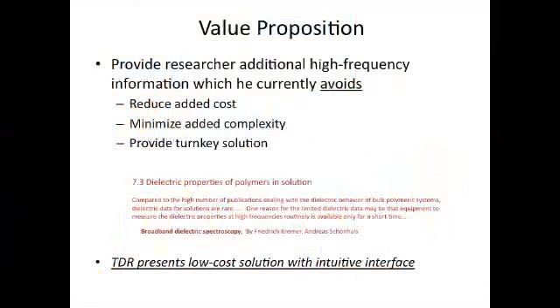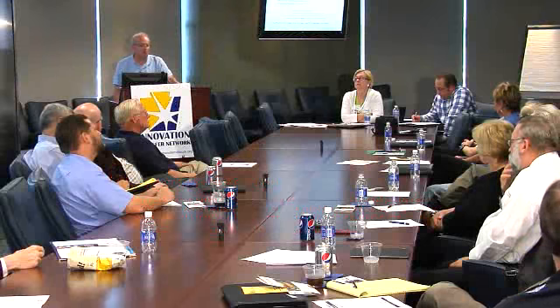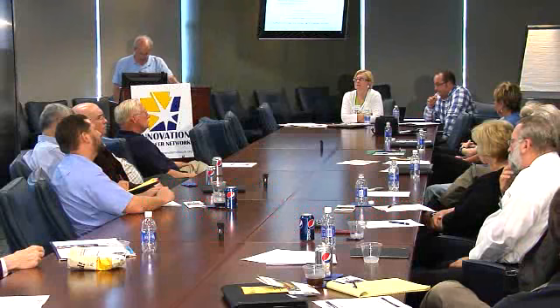The value proposition amounts to providing the researcher additional high-frequency information which they currently avoid. We reduce the added cost compared to something like a vector network analyzer, minimize added complexity, and the time-domain approach is more intuitive — you can window out the sensor response from extraneous artifacts in the connecting lines. As one source noted, dielectric data in solutions is rare due to very limited equipment in this area, and TDR presents a low-cost solution with an intuitive interface to expand researchers in this area.